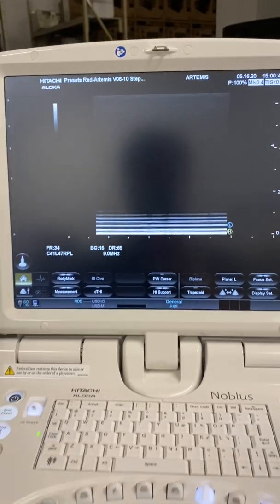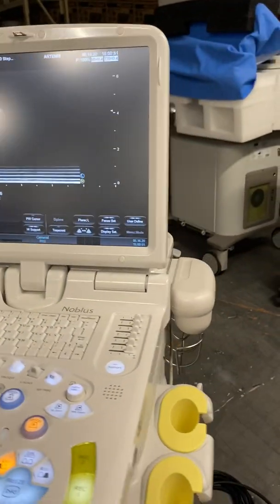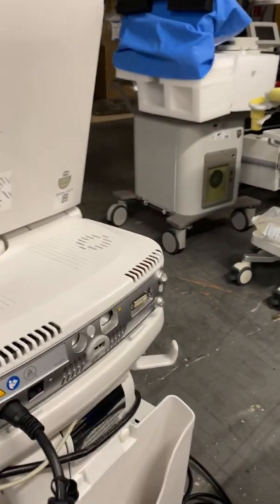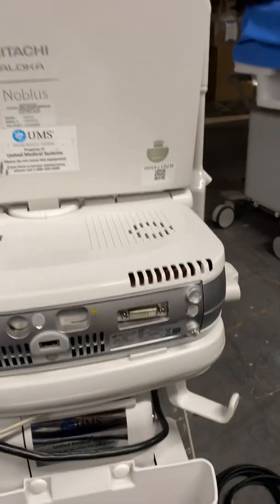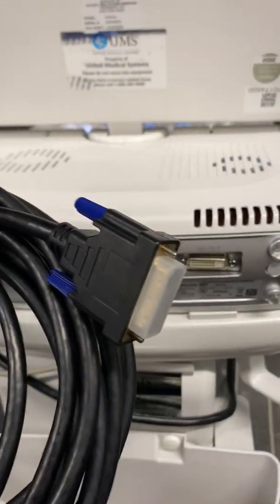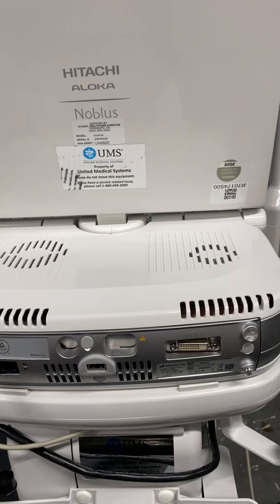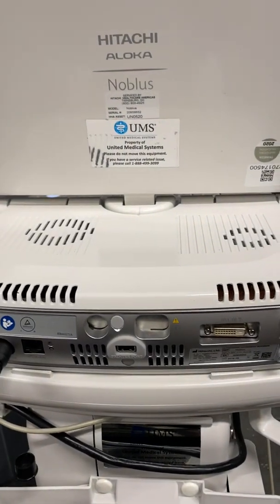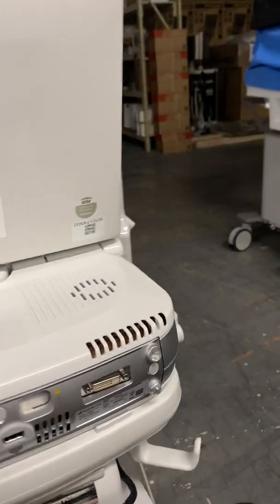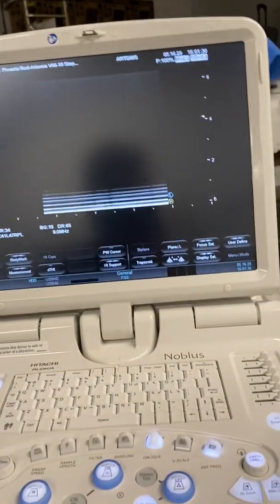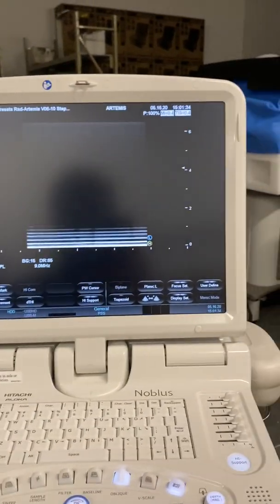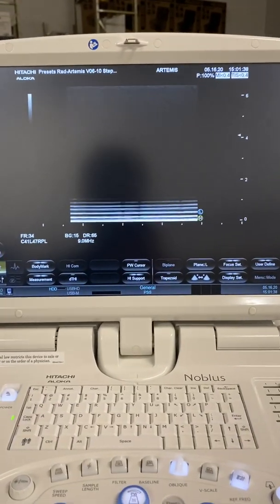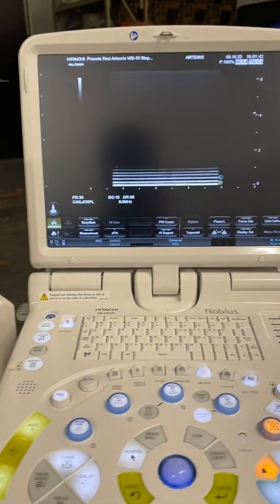So this concludes how to set up the probe on the ultrasound. One thing that might come up is if the doctor wants to use a rolling monitor in the OR to see better. You can plug the DVI cable into that port just like you would for the regular fusion biopsy. Plug it into this port, and the other end of the cable goes into the DVI input on a rolling monitor. Then you would just set the input on the monitor to DVI in. And the staff in the room should know how to do that. That way you can position the monitor above the patient, and the doctor can look straight at the monitor instead of having to turn his head and try to see on this smaller monitor. But it's up to the urologist. If they want to do that, that is possible. And that concludes how to set up the ultrasound for SpaceOAR or transperineal fiducial markers.